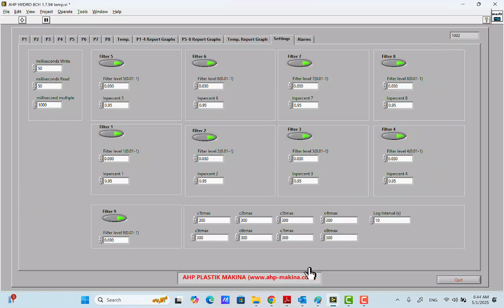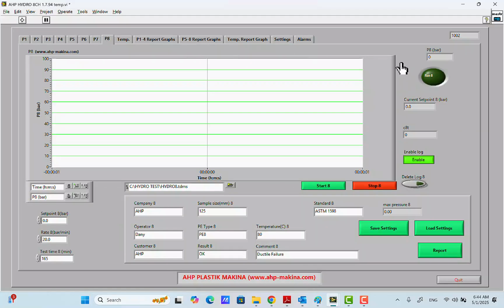Here on the setting, you have another function, log interval. Now it is set to the default of 10 seconds. When you have an 8 station machine, and in every second you are receiving and sending data from the CPU of the pressure tester, and you want, for example, to do the test for 1000 hours for each line, you will have a huge amount of data, and it will be difficult for the computer to manipulate this data in real-time mode because all will be going to the RAM of the computer.